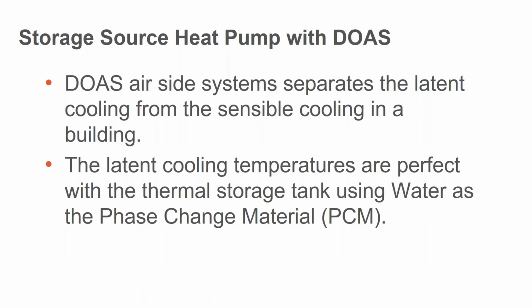So let's take it another step further. A lot of systems now are being designed with DOAS systems, which essentially, on the cooling side, separate the latent cooling from the sensible cooling in a building. So they have two different coils. One hits the fresh air that's coming into the building. You take all the latent or most of the latent out of that. And then the sensible coils are in the different zones, and we do the sensible cooling there.